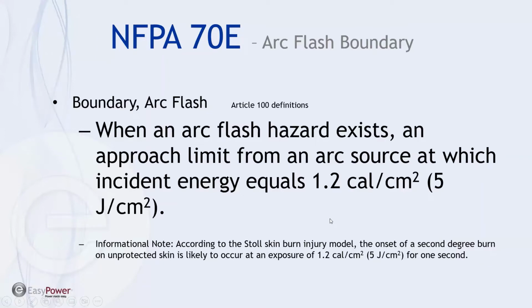Now, NFPA 70E also defines what the arc flash boundary is, and this is under the definitions category. When an arc flash hazard exists, it's the approach limit from an arc source at which the incident energy equals 1.2 calories per square centimeter. Now, this is not a number that's been picked out of the air. It's actually the result of studies that were done by exposing human skin to different levels of heat flux. And it was determined that 1.2 calories per square centimeter for 1 second was the level of exposure at which there was a 50% probability of second-degree burn.